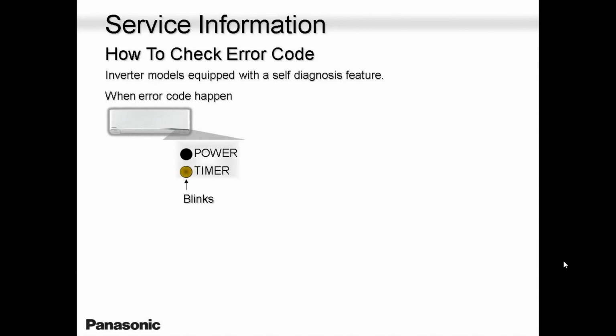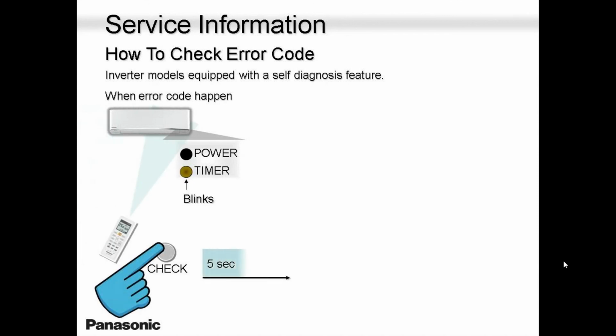If they tell you it's H11 or H97, you know what to do. For example, H97 is fan motor, outdoor fan motor. So at least if it's a 2-hour drive, you can go there with an outdoor fan motor, or maybe even the outdoor PCB, depending on the situation. So how do you do that?